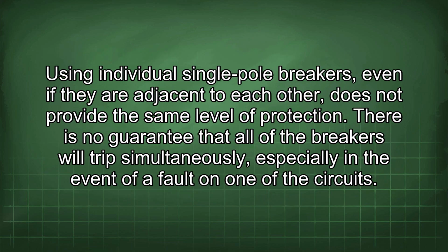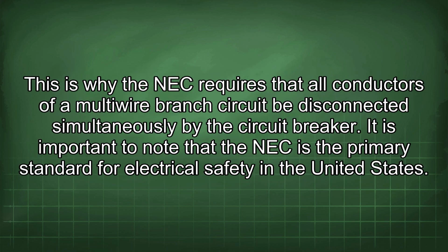Using individual single-pole breakers, even if they are adjacent to each other, does not provide the same level of protection. There is no guarantee that all of the breakers will trip simultaneously, especially in the event of a fault on one of the circuits. This is why the NEC requires that all conductors of a multi-wire branch circuit be disconnected simultaneously by the circuit breaker.